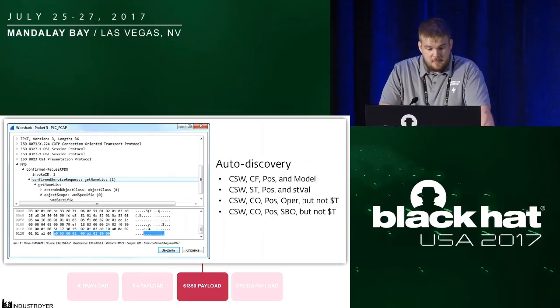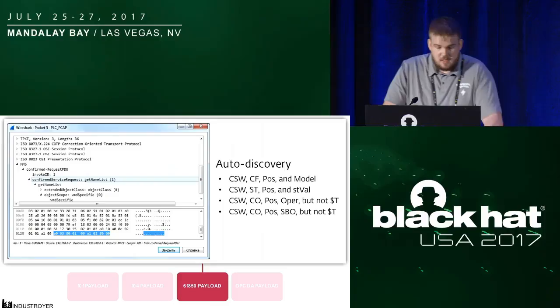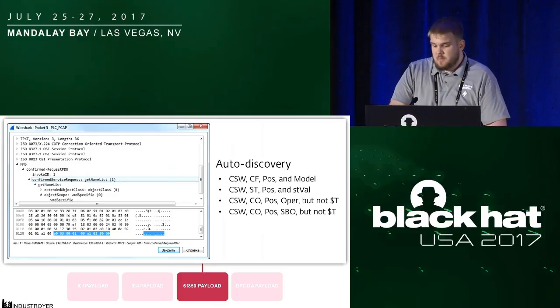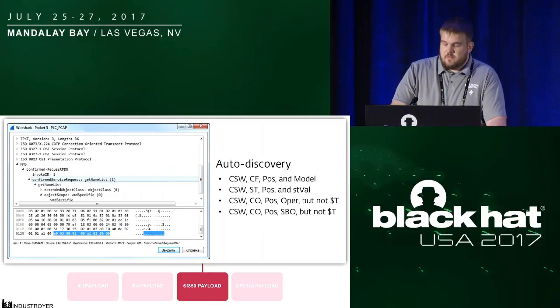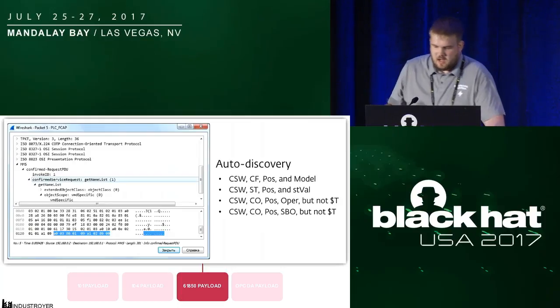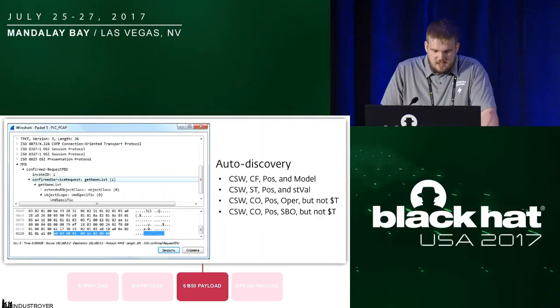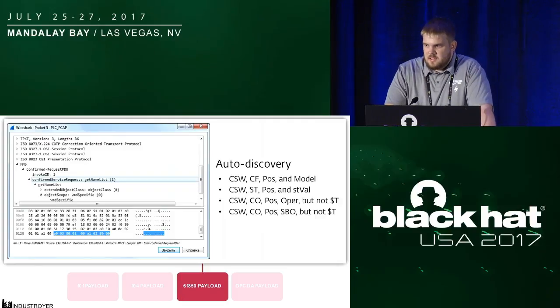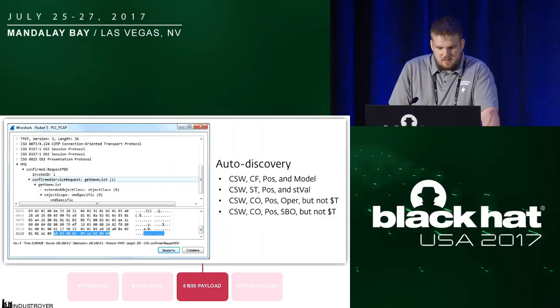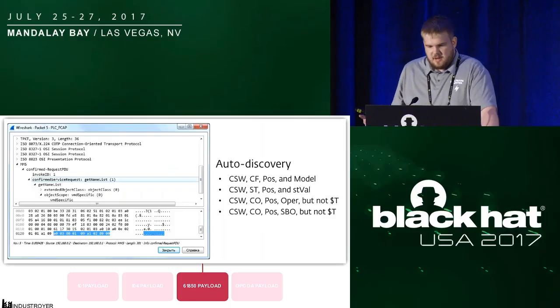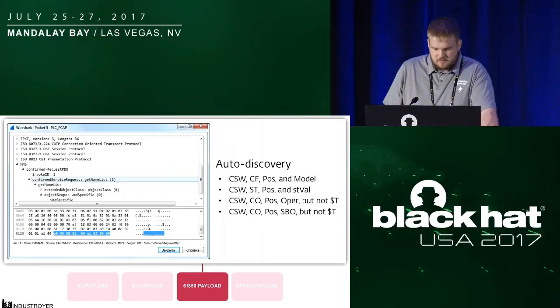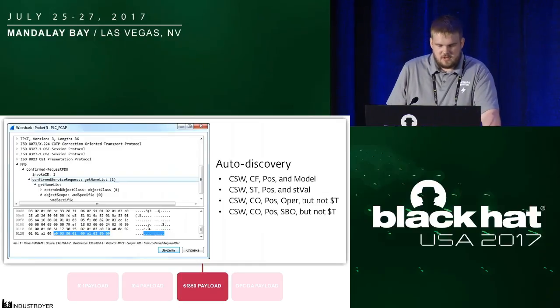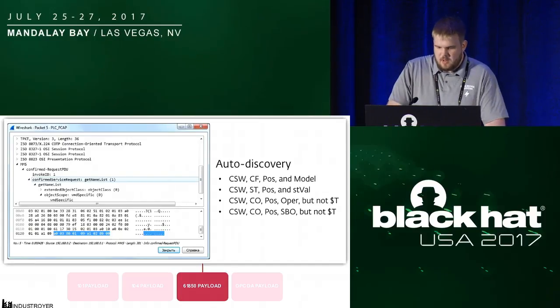61850 is a bit different and more advanced. Like 104, it operates over TCP/IP, but it can function even if IP addresses are not defined, because it has an auto-discover feature. It can discover relevant devices by scanning the IP range for a host that has open port 102.